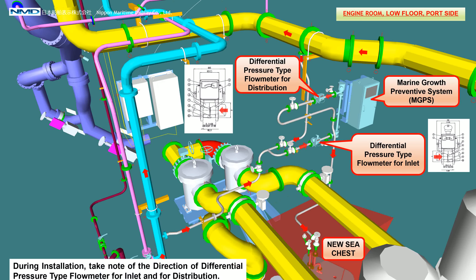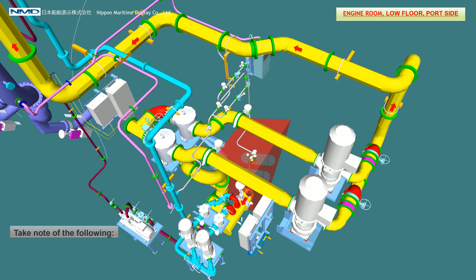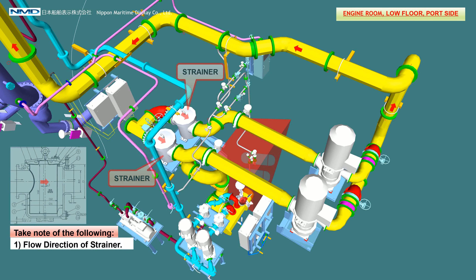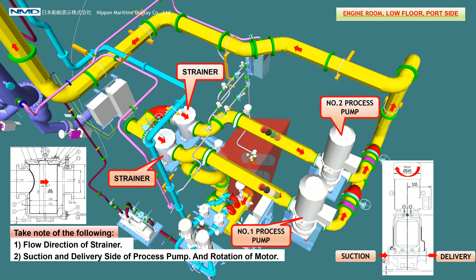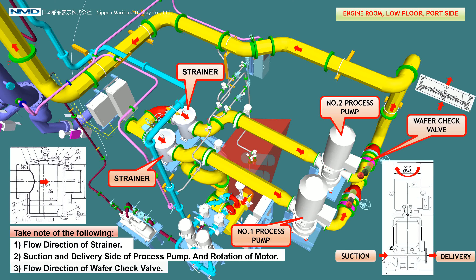During installation, take note of the direction of the differential pressure type flowmeter for inlet and for distribution. Also take note of the flow direction of the strainer, suction and delivery side of the process pump and rotation of the motor, and the flow direction of the wafer check valve.